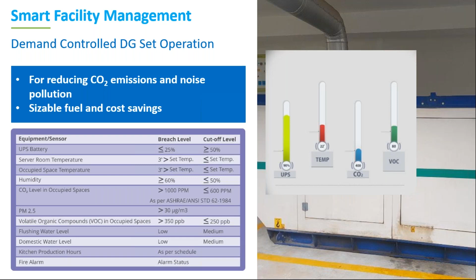In the same way, after the genset gets switched off, maybe half an hour after the power shutdown, it runs for an hour or so. Once good indoor levels and battery levels are reached, the DG set gets switched off automatically. So we found that when there's a power shutdown of 8 to 10 hours, our DG set runs only for a maximum of 4 hours, resulting in a good amount of CO2 emission reduction.